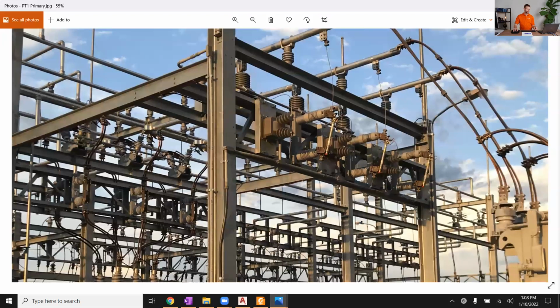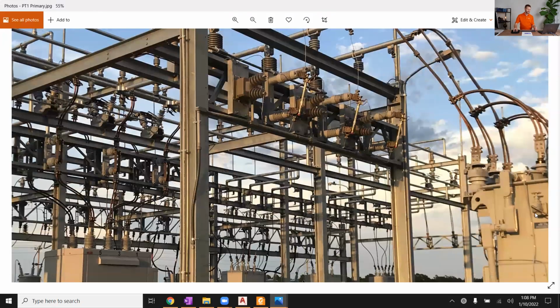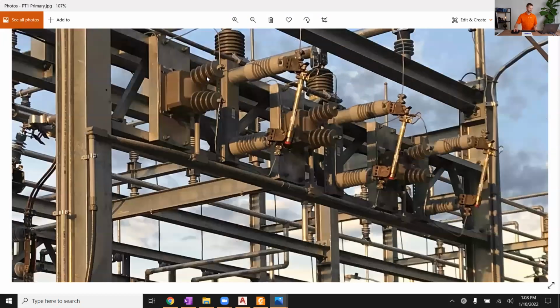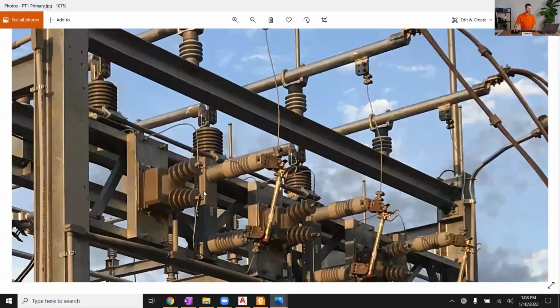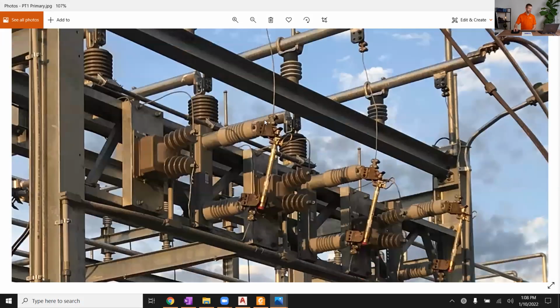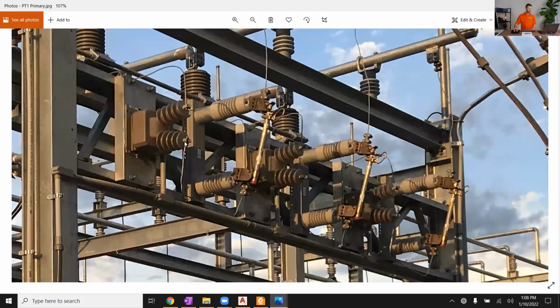Sorry about that. This is a distribution class. This is a transformer coming off to a low side bus. And so this is effectively like a bus PTs. And so we've got the primary system coming down here through the fuse, coming over to one bushing of the PT, and then the other bushing is neutral, which is grounded. So that's measuring the phase to neutral voltage across this PT. There's three of these, one per phase.